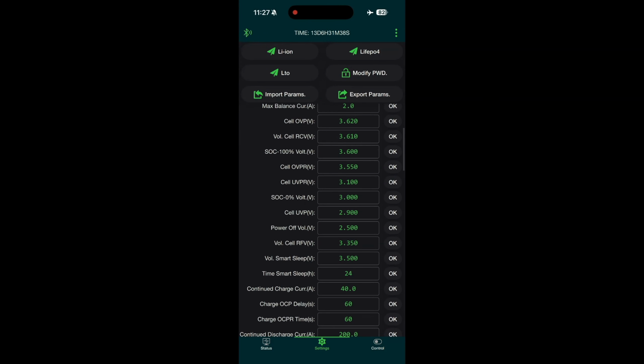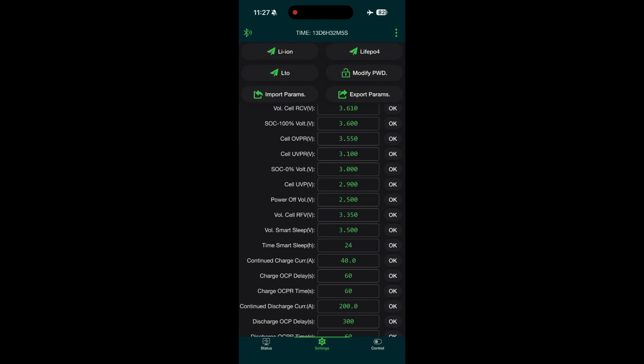Cell RFV stands for reference float voltage. This is basically a communication setting — if you have communication with your charger or inverter, the charger will go into float mode after the absorption charging phase.